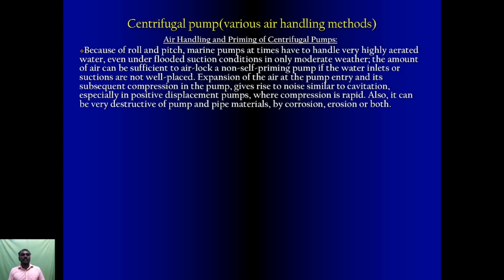Centrifugal pump: various air handling methods, air handling and priming of centrifugal pumps. Because of roll and pitch, marine pumps at times have to handle very highly aerated water, even under flooded suction conditions in only moderate weather. The amount of air can be sufficient to airlock a non-self priming pump if the water inlets or suctions are not well placed.